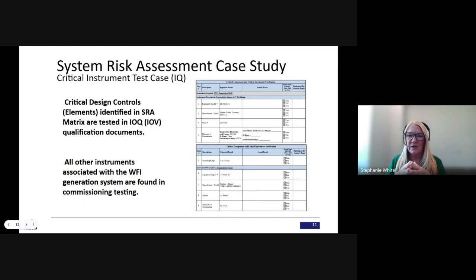Those six elements we pulled forward into a protocol, so here we have just an IOQ test case where we have our critical components. Remember, instead of doing a component assessment, the system risk assessment helps us identify those critical components. Because we had an immature engineering department, or maybe the vendor documentation wasn't what we wanted, we pulled those elements forward into a protocol.